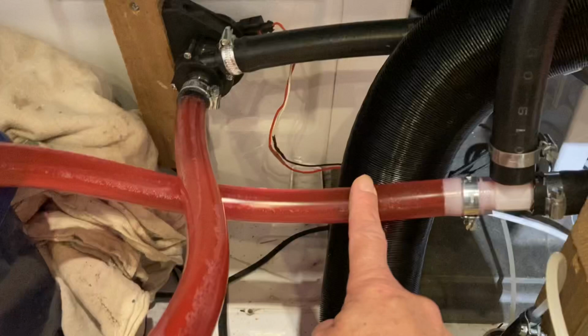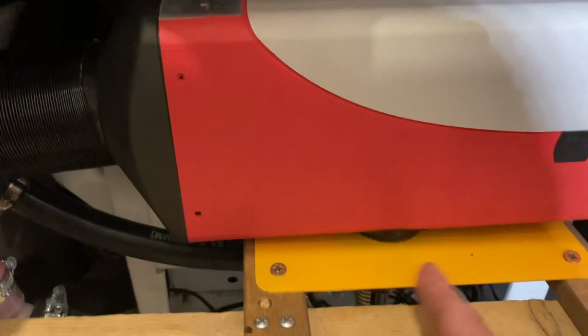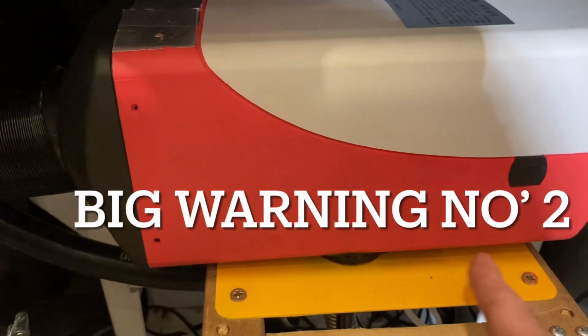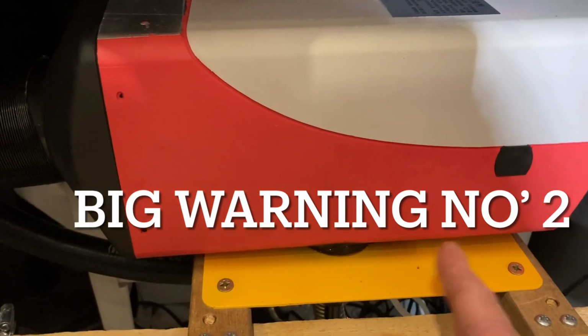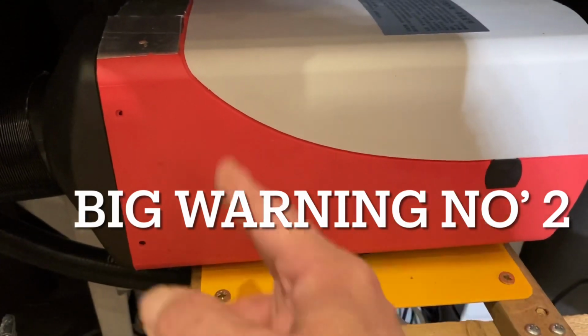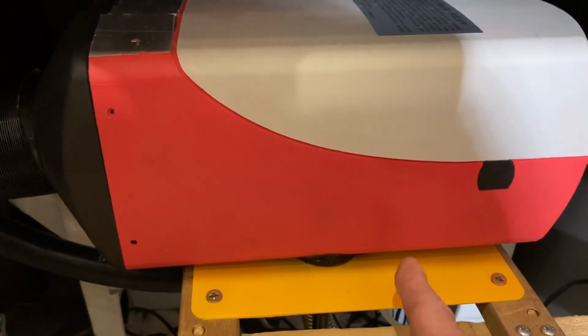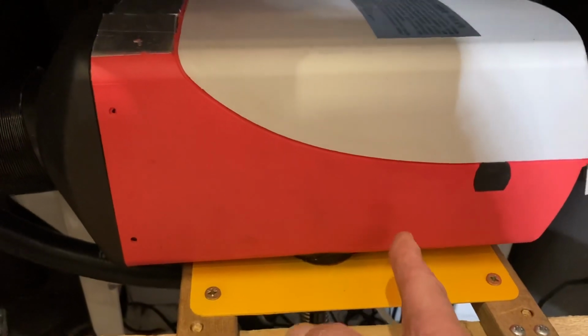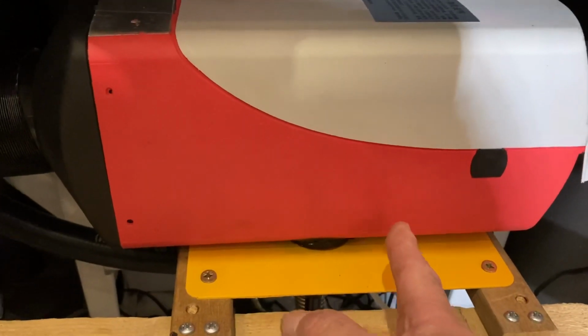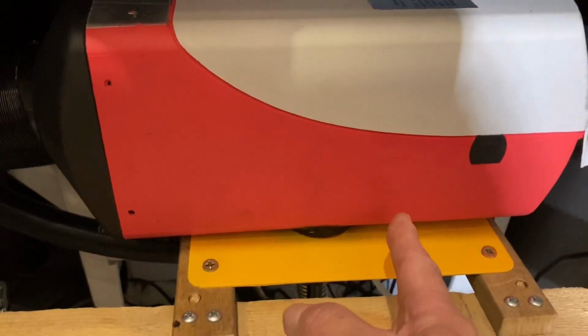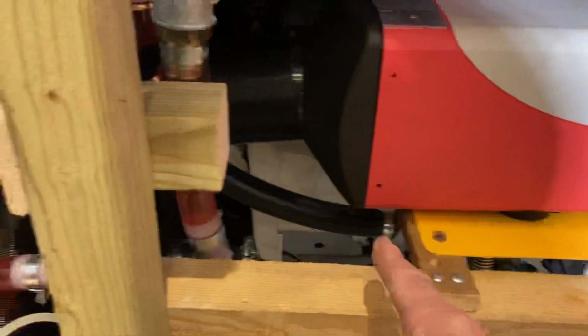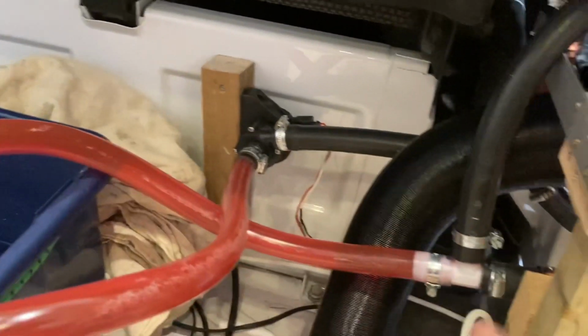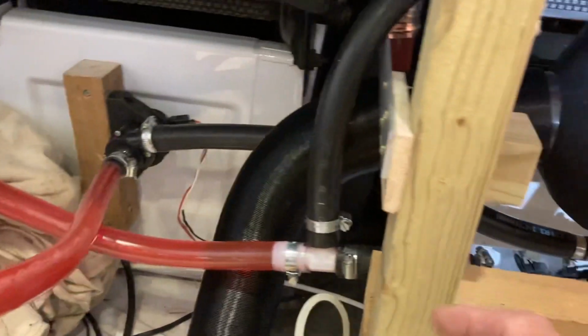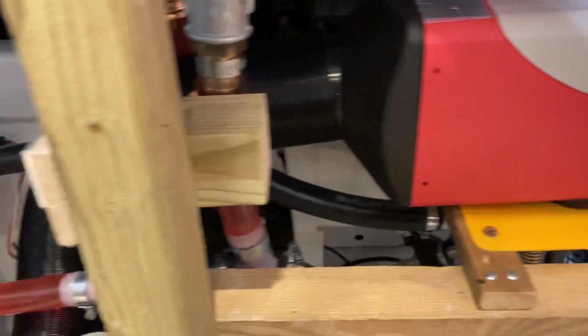I showed you the air travelling in these pipes when I turned it on. If I was to turn the pump off, inside at the bottom where the heat exchanger is, it would start gassing up, because it can get up to 150-160 degrees C inside, and water boils at 100, so it instantly starts to fizz up. The fizz turns to big bubbles, the bubbles turn to gas, and the gas eventually turns to steam pressure, which shoots down these lines and blows your pipes off on all the Jubilee clips and everything - it'll make a right mess of your camper van.